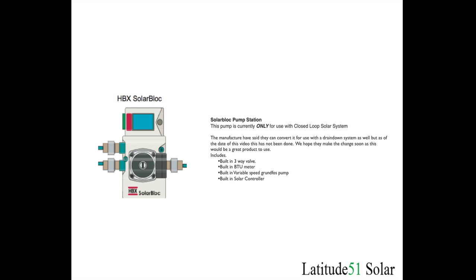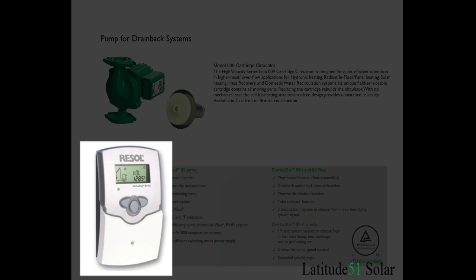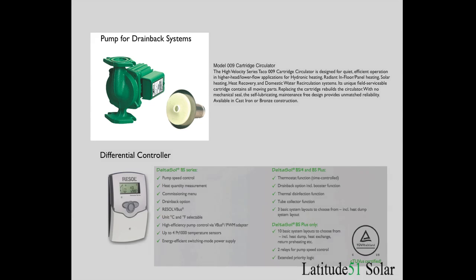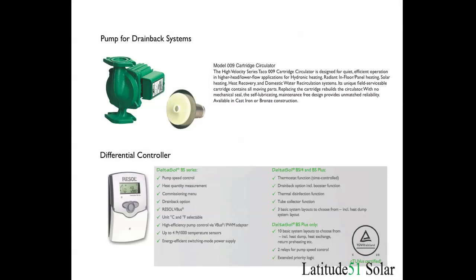If you want to use a drain down system you use some slightly different equipment. The controller is basically a differential controller which will allow the pump to be turned on or off. An example of one you can use is the Resol controllers, which can be used in both closed loop and drain back options. The pump system, such as this Taco model, works for solar systems because it allows the fluid to drain back through the pump when it turns off. Some pumps won't allow back flow when the fluid turns off, and you can't use those for a solar system, so make sure you get a suitable pump if you are going to use a drain down system.